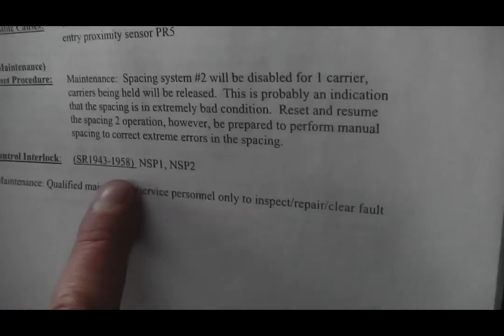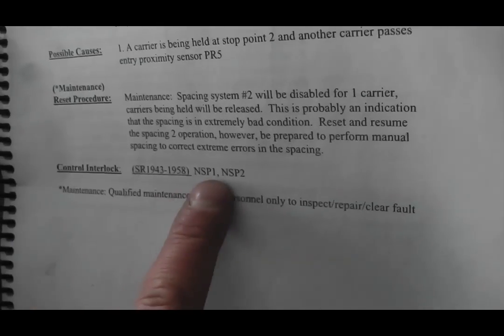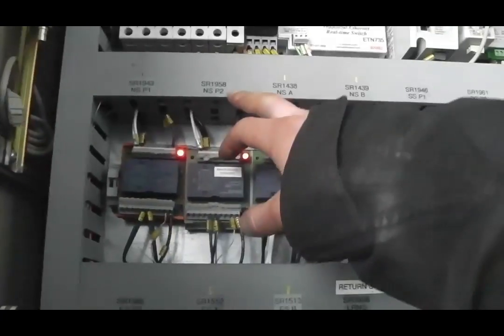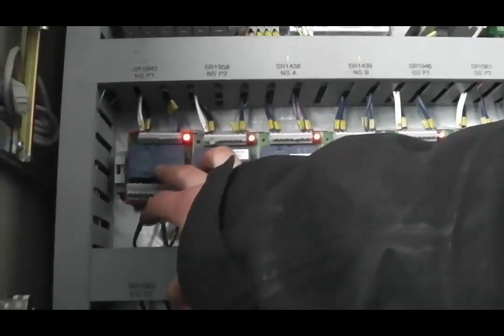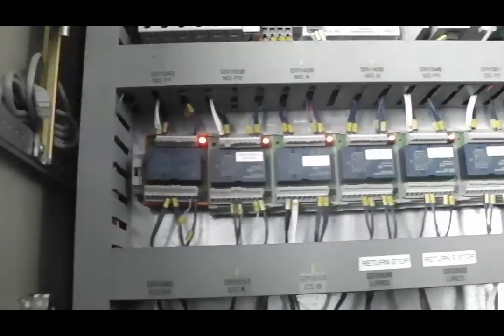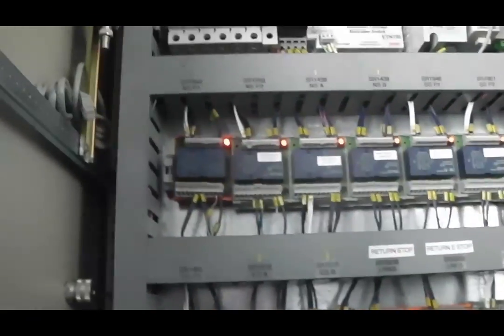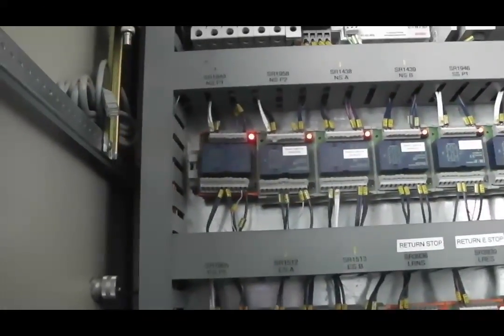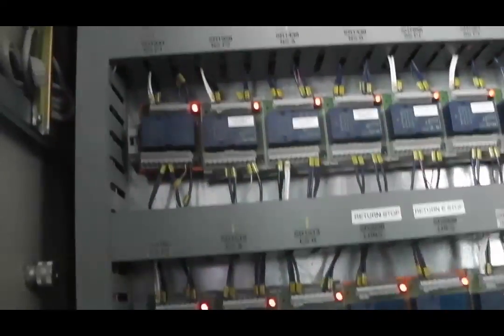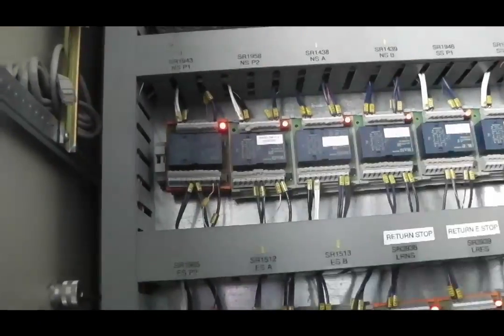So this one here has a couple of relays that we need to check and make sure they're fired. NSP-1 and NSP-2. We have NSP-1 here and NSP-2, correctly labeled. Those ones are fired, obviously, because we don't have a service break. We only fault on the left right now. If we did, then these two relays here would be out.